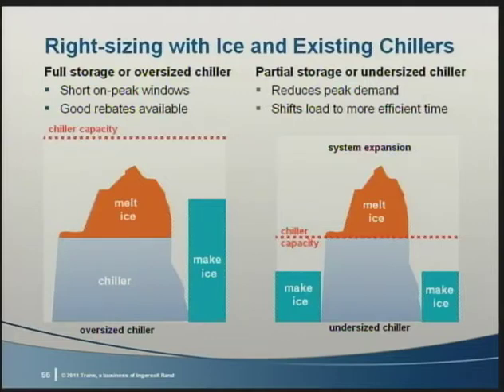Another key point on existing systems is eliminating the glycol penalty on existing cooling coil performance. Reducing the supplied fluid temperature restores full coil capacity without increasing pumping or fan energy costs. An extra slide included in your handouts shows the reselected existing cooling coils. So that's it for the overview on adding ice to a positive displacement chiller system. Mick, what other system retrofit options are there?